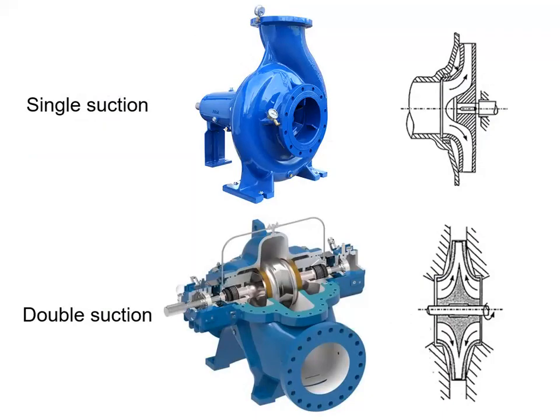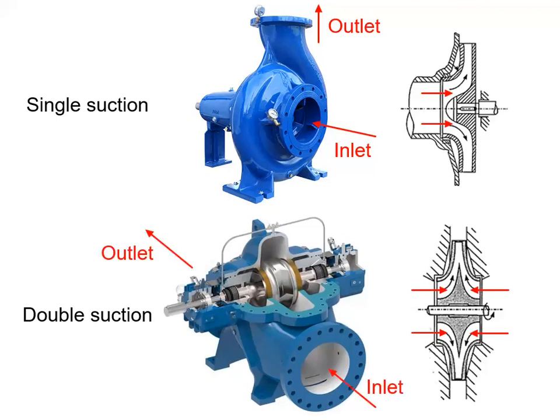Here we see a comparison of single suction and double suction type centrifugal pumps. In the single suction type, the fluid enters the space between the blades only from one side. There is only a single eye opening. The inlet and the outlet are parallel and perpendicular to the shaft, respectively. In the double suction type, flow enters the space between the blades from both sides. There are two eye openings. Both the inlet and the outlet of this pump are perpendicular to the shaft.